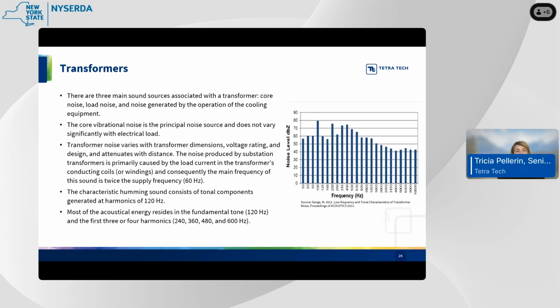The noise produced by substation transformers is caused by the load current in the transformer's coils, attributed mainly to a frequency that's twice the supply frequency. That's the humming noise you're used to hearing, which usually consists of tonal components generated at harmonics of about 120 hertz.